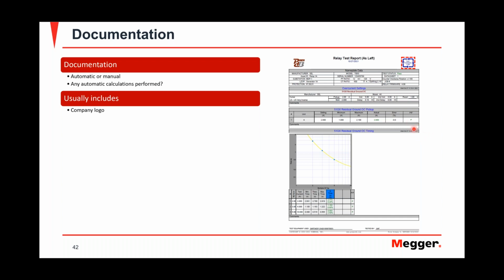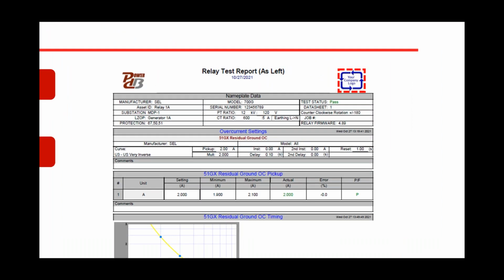So ultimately, this is one of the most important things that, in my opinion, gets overlooked: the criteria for passing or failing. Sometimes you have to understand what to expect and what the boundaries are for that expectation. What's the minimum and the maximum? Having documentation that allows you to see that, and allows the customer to see that, is one of the most important things, because at the end of the test, that customer is going to receive this report, and the first thing he wants to see is that test status. Did it pass or did it fail? That's the first thing everybody looks at.